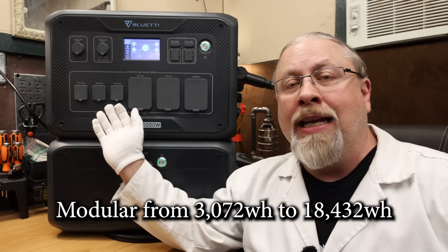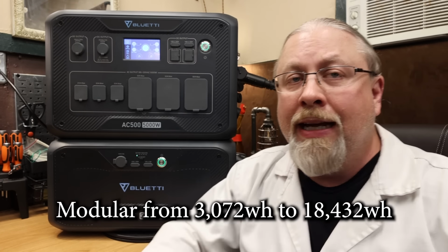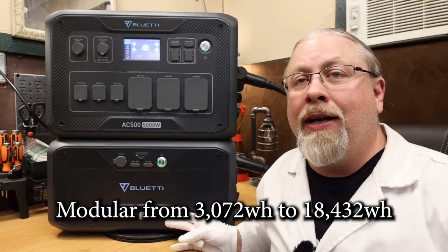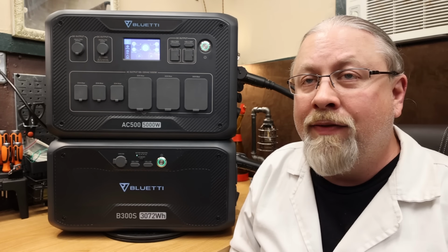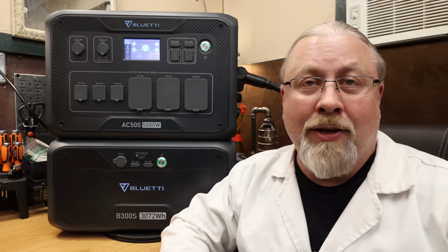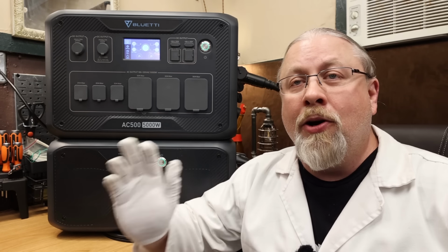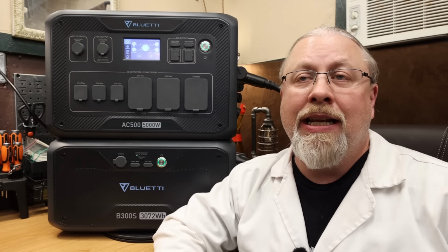Now the AC500, just like its previous little brother, the AC300, is a fully modular design. This one allows you to add up to 6 3,072 watt hour batteries, and these are lithium iron phosphate rated at 3,500 cycles to 80%, for a total capacity of over 18 kilowatt hours.